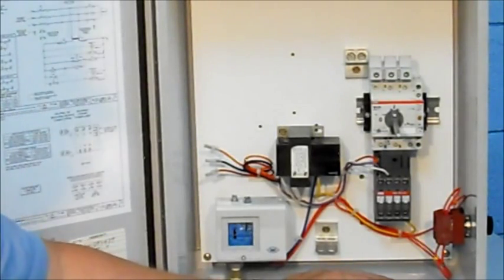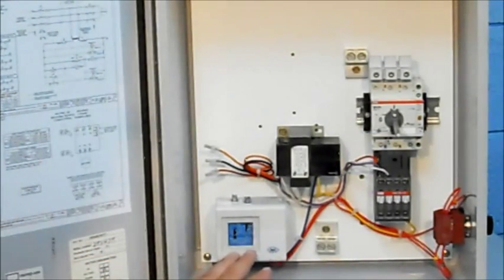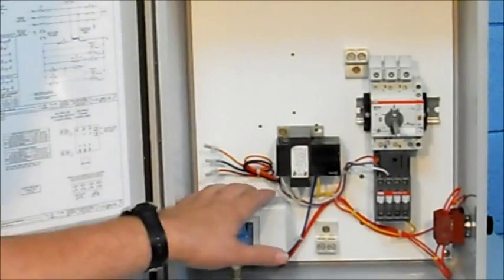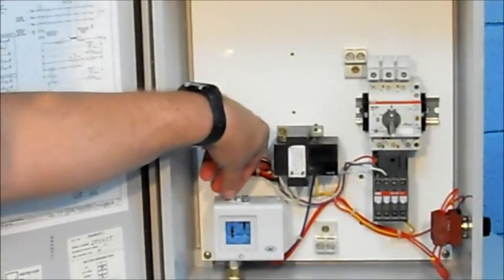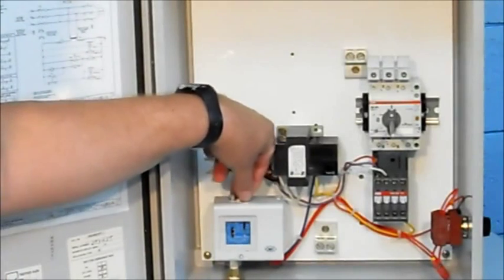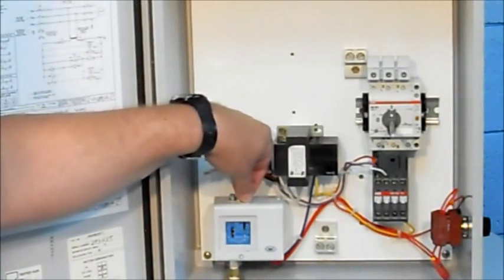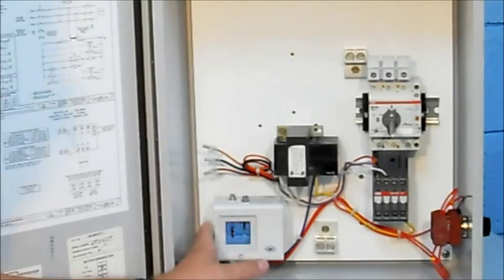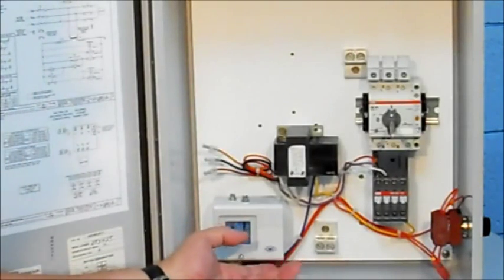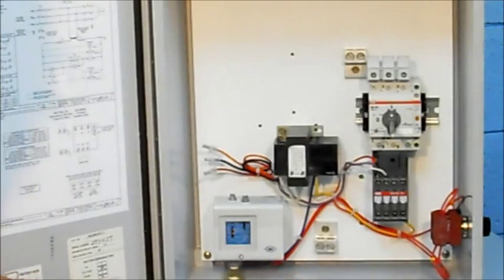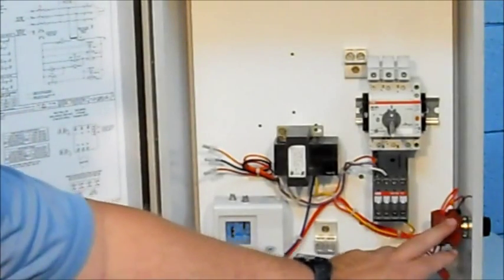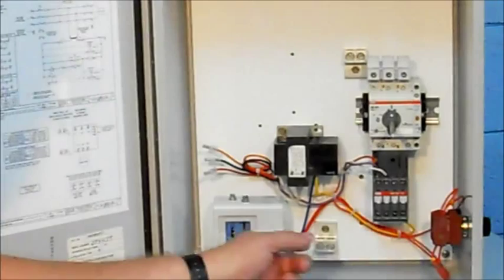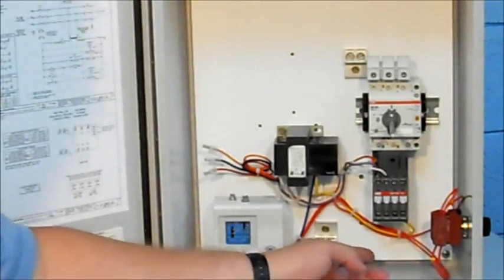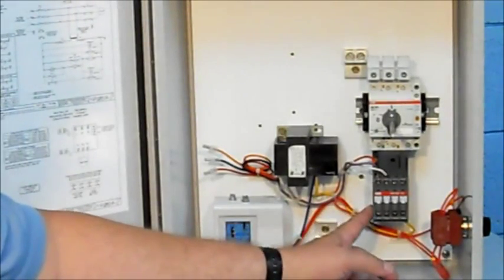For automatic operation, there is a pressure switch located inside the controller, and you can adjust your cut in and cut out pressures based on these two knobs at the top. This one determines your cut out pressure. This one determines the differential for the cut in. By adjusting those two, you can determine exactly where the pump needs to start and stop. Move your selector switch to the auto position, and that brings the pressure switch into the loop to control the voltage going to the coil.